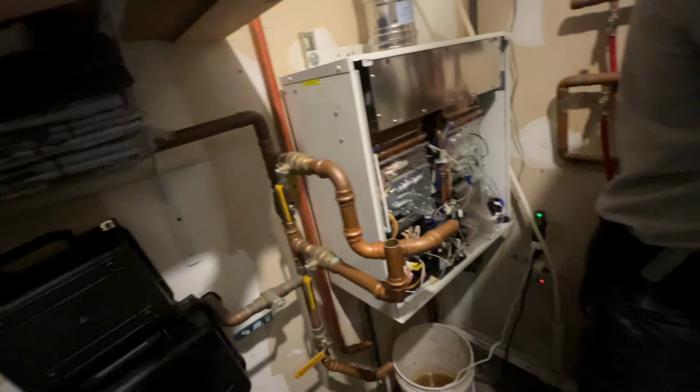Okay, so here's the new heater, much smaller than this one, but we're getting all of our fittings on the heater taped and doped. You can see the size difference. It's pretty different. But this is 380,000 BTUs. This is 199. This is immensely oversized. 2 heat exchangers. It's a big house, but it's not big enough for a commercial water heater, because that is a commercial water heater. This is 199.